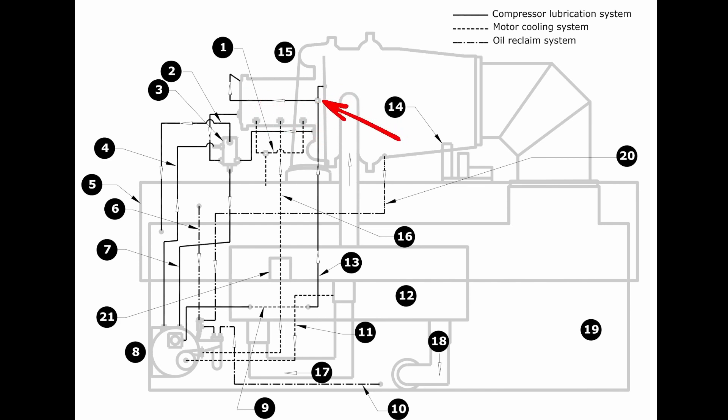This journal bearing is essentially, think of it as like a sleeve bearing, but it actually has oil injection ports that we use. The oil acts as our rotating surface. With a regular sleeve, we're not going to actually be injecting oil. It is just a permanently lubricated bearing surface. With an actual journal bearing, we're actually injecting oil into the bearing assembly in order to create a rotating surface. The oil itself acts as that.